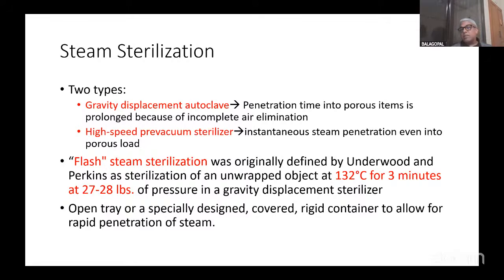Here I would like to mention flash steam sterilization, which was originally described by Underwood and Perkins for quickly sterilizing unwrapped objects at a temperature of 132 degrees centigrade for 3 minutes, applying a pressure of 27 to 28 pounds in a gravity displacement sterilizer.